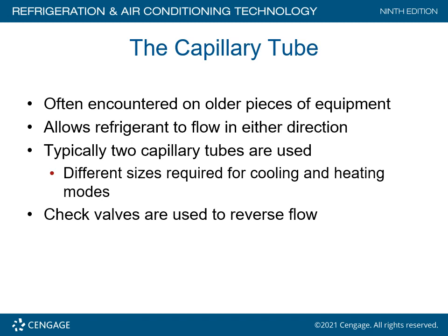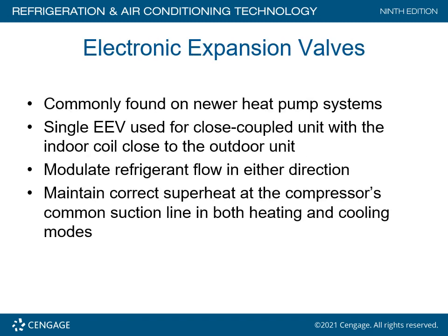Capillary tube. Often encountered on older pieces of equipment. I really doubt if you're going to see one of these. I haven't seen a cap tube heat pump system in quite a while. Allows the refrigerant to flow in either direction. Typically two capillary tubes are used, different sizes, one for cooling and one for heating modes. Check valves are used to reverse flow. You will not see these in present day heat pumps.